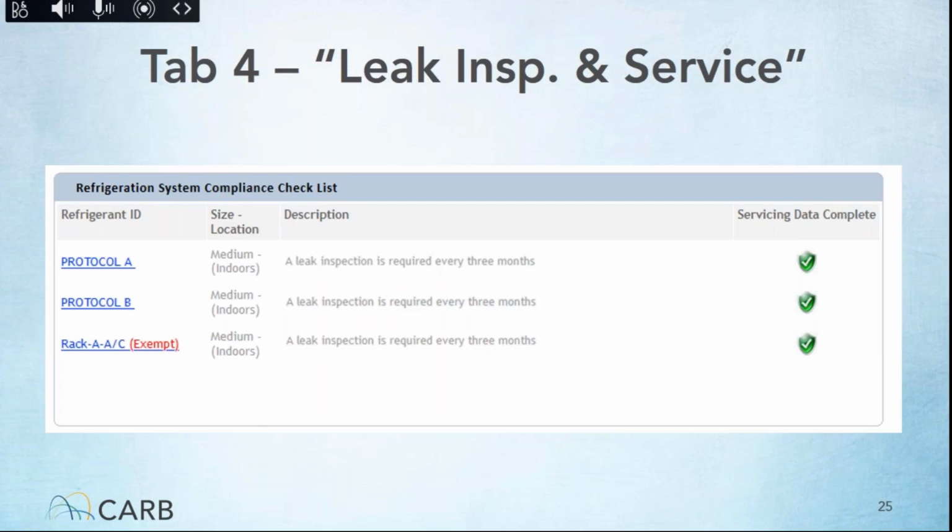It's not a solid plus or minus 20 days, but it does give some wiggle room for people. As I was alluding to earlier, we're not here to punish somebody if they're a day late on their leak inspection or if they're a couple days premature. We built into the system some wiggle room with that, so we almost have it going up to 3.9 months. With that logic, it is possible for someone to have 3 leak inspections spread out perfectly in the year and still pass for that year as well.